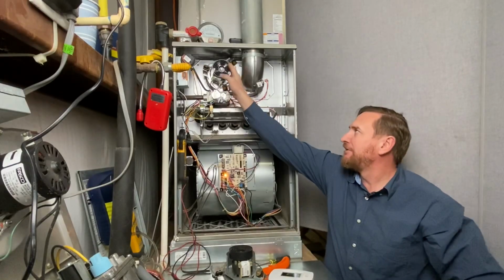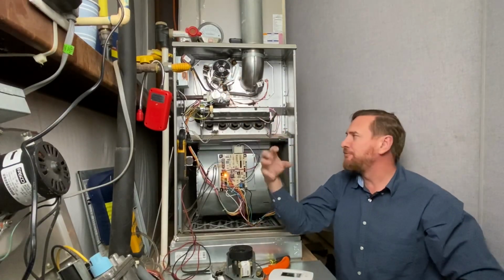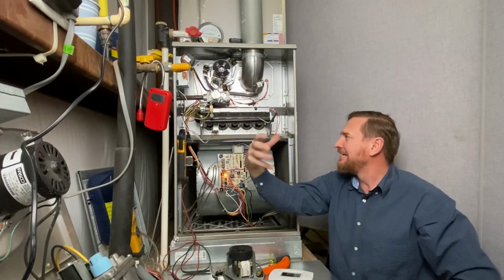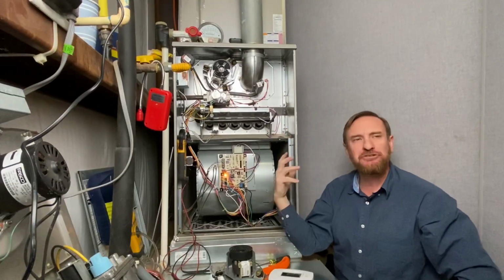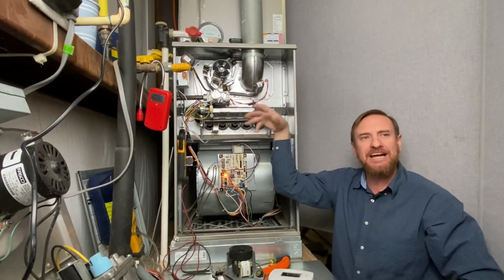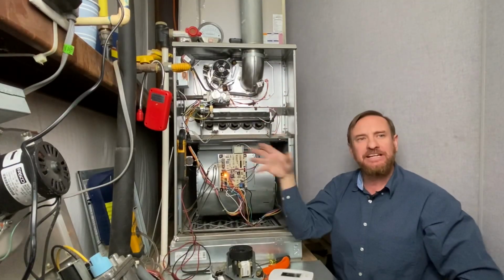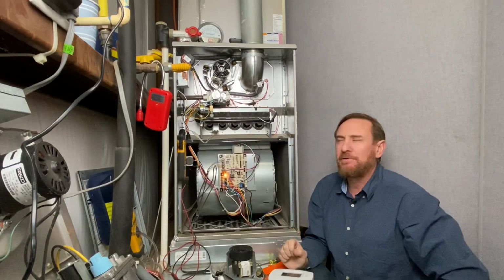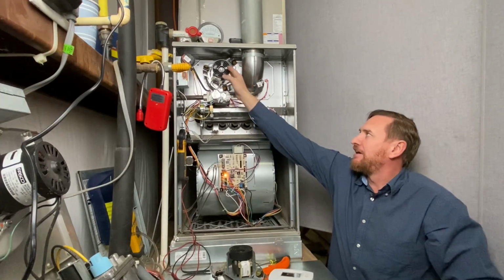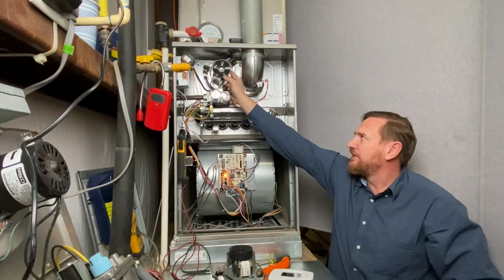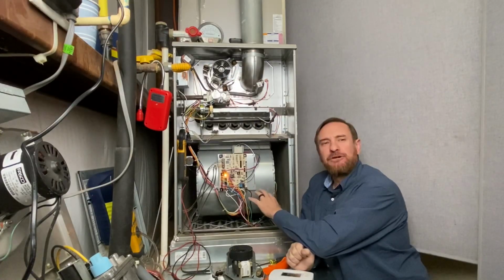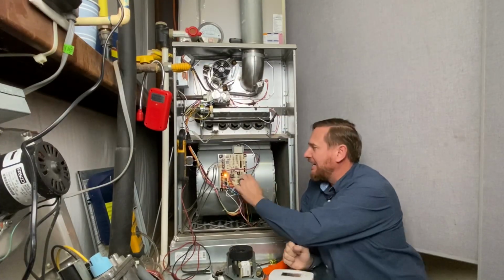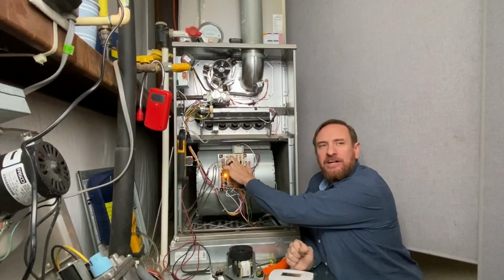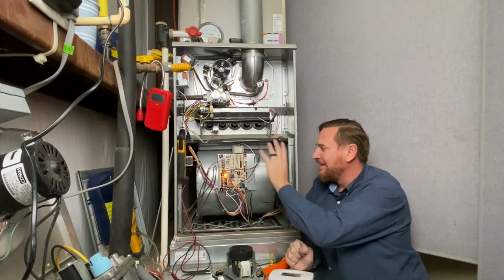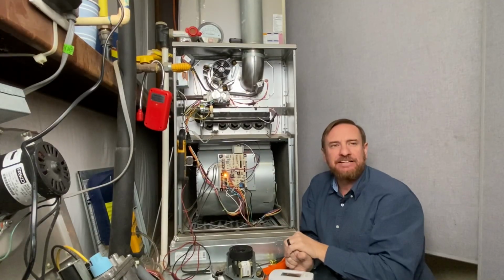But if you notice, this motor kept running, and what it wants to do is post-purge, post being after, clean out the heat exchanger. Any of those fumes that are in there, it wants to help pull those fumes out of the heat exchanger, get some of the clean air in there, so that way we're ready for that next process for heat. Once it's done that, few seconds, it shuts this off. It keeps that blower running to cool off the heat exchanger, and that's what some manufacturers allow us to adjust, that off cycle. Now the system's off, ready for the next cycle for heat.